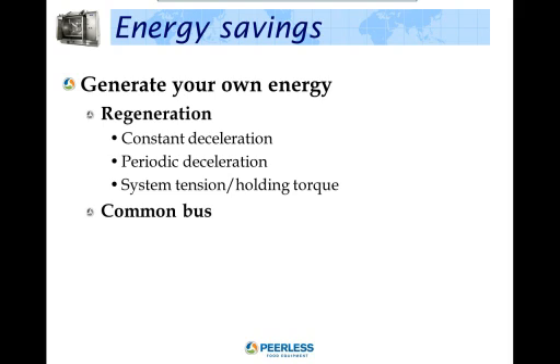System tensions and holding torque. When two sections of a machine are used to create tension on a material between them, such as on a metal strip or in a strip mill, the two sections may be running at the same speed, but the process requires a certain amount of tension on the strip to run properly. This means the lead section will run in the forward direction and pull the strip, and the following section will also run in the forward direction while at the same time providing the needed torque in the reverse direction of the strip, thus creating the proper tension.